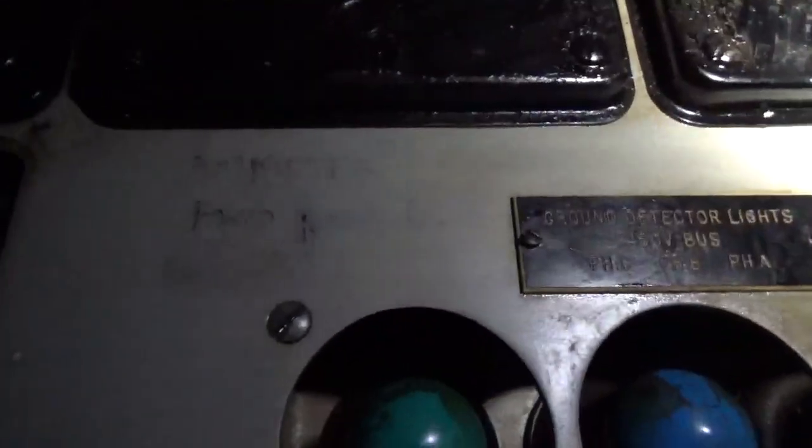So I have a few more of these face plates to go. Let the water drain out. I've tried to label them but my pen is getting caught in the grease and it's smearing, but at least we know. Look at that — we got some leakage right out of this one and I haven't even opened it yet. Voltmeter 120 volt DC bus tie feeder. And then we got those two up there. Obviously these open. I can't even tell how much degradation is here.